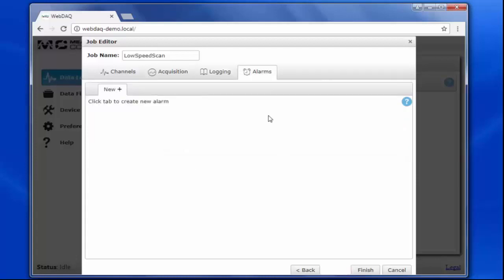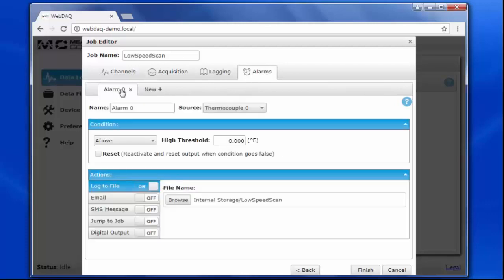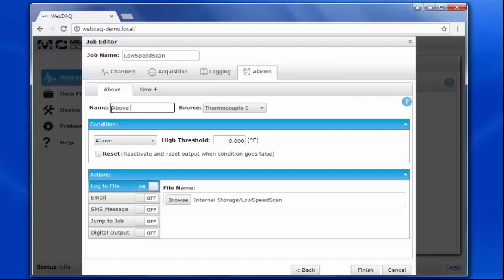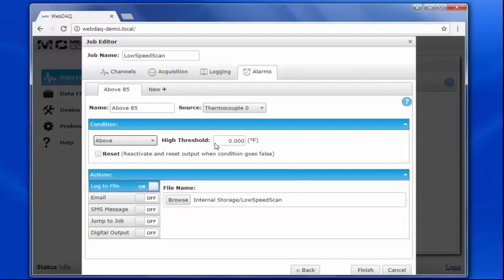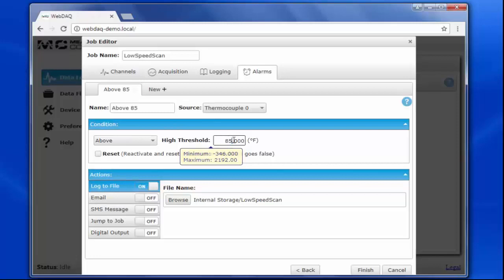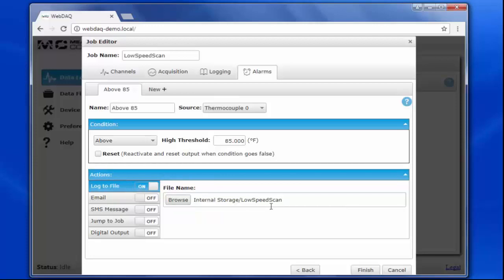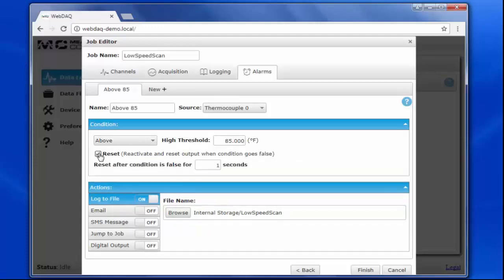The final option is to configure any alarms. Let's say I want to be notified if the temperature exceeds a certain threshold. I'll set the alarm condition to above 85 degrees. And I want the alarm to be logged to my data file. I also want the alarm to reset once it's false, so that I get another notification if the temperature goes above 85 degrees multiple times during the job.